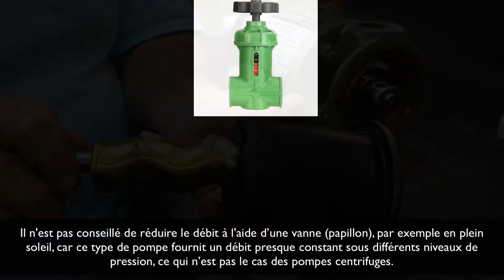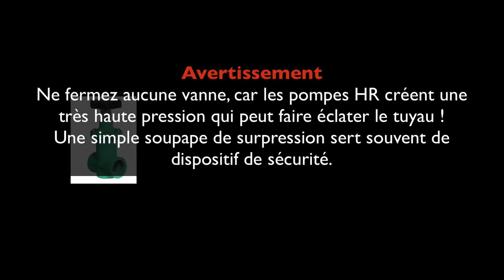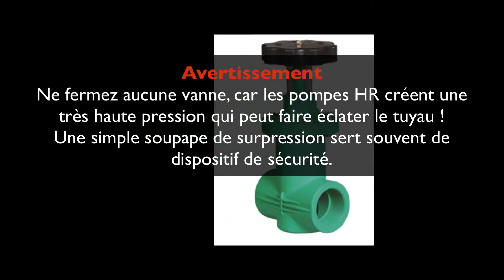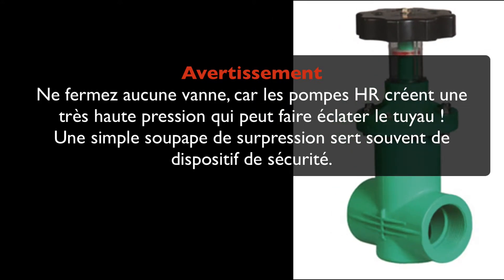It is not advisable to reduce the flow rate with a throttle valve, for example in bright sunshine, since this pump type delivers a nearly steady flow under different pressure levels, which is different to centrifugal pumps. Warning: do not close any valves, because the HR pump will create very high pressure which may burst the pipe. A very simple pressure relief valve is commonly used as a safety device.